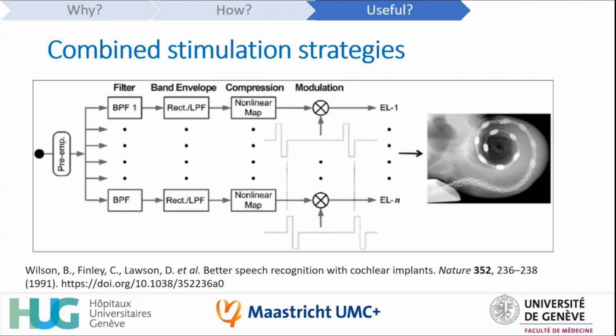And these are important because our vestibular cochlear implant has very particular technical constraints. And why is that? First, of course, because it's a combined device that has to stimulate the auditory system and the vestibular system. And if you remember the stimulation strategy of cochlear implants, they use a strategy called CIS, continuous interleaved stimulation strategy, where each electrode is stimulated at a time at a very high rate.